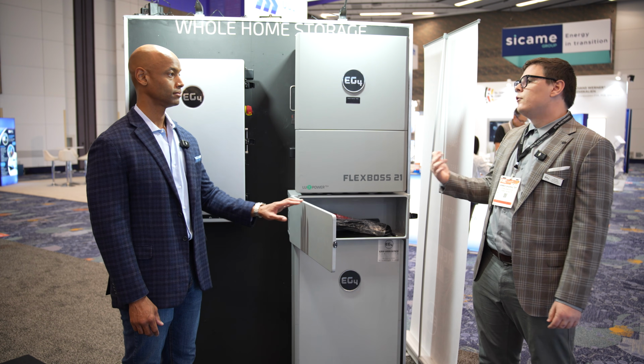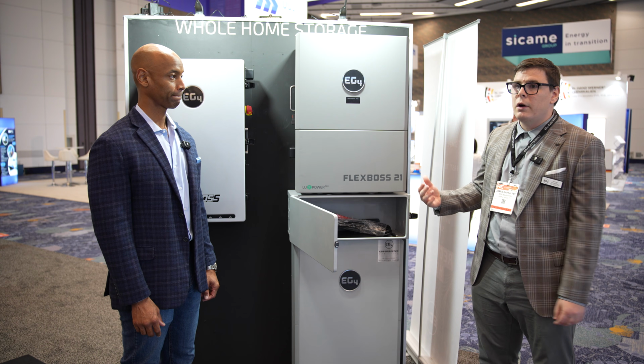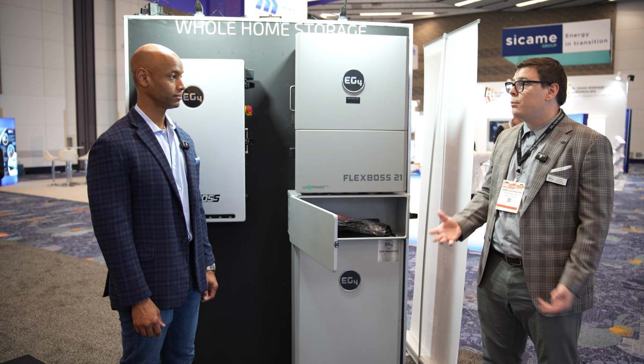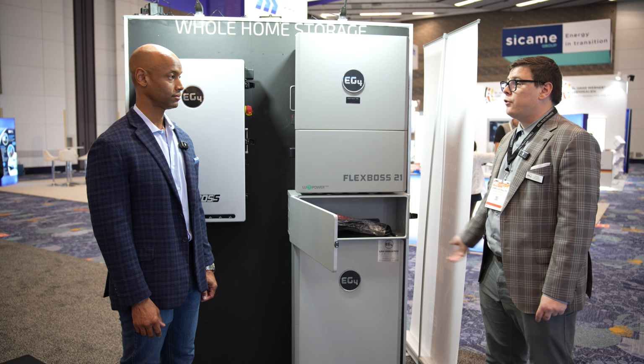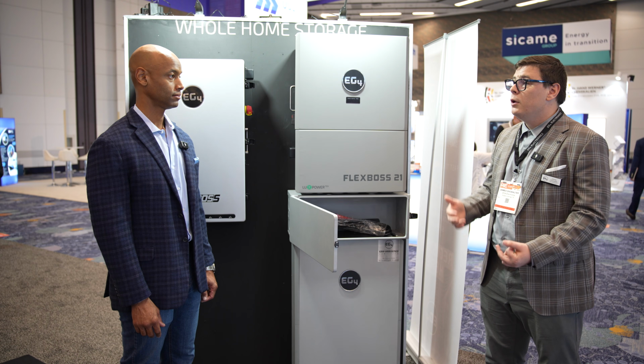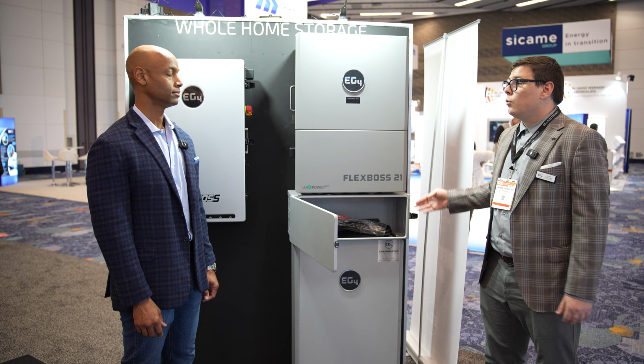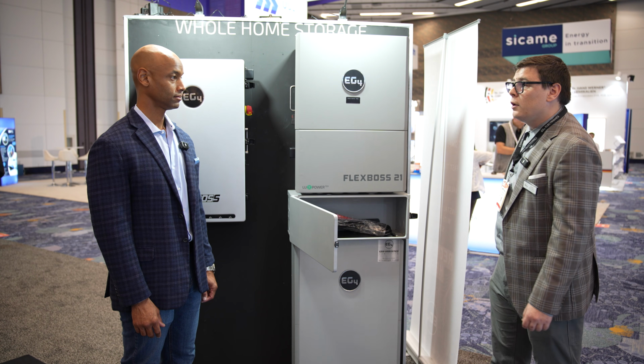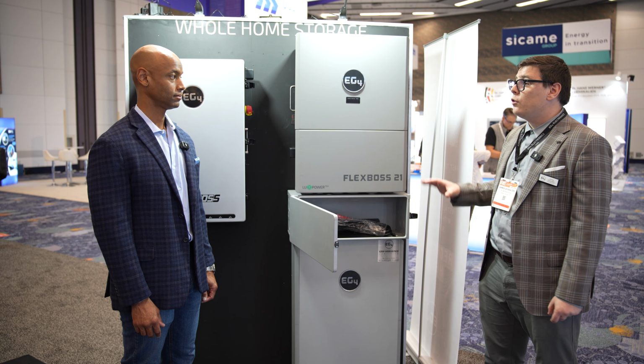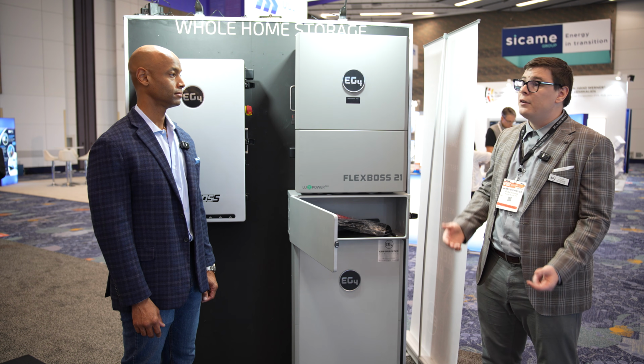We found this with the do-it-yourself and beginning community: the number one cause of failure is people not using proper torquing on DC buses. So we took that option away from them and moved to UL listed quick connects. We have 250 amp quick connects on a 600 amp bus bar, and we can do up to 5 batteries without needing additional wiring.